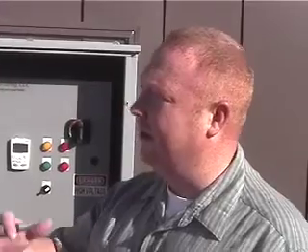Well, that's a very good question. The way this works is we have two different building pressure sensors and a total of 5 relief fans. I believe it's 1, 2, and 5, which is in the middle of the building, and they're the main ones that do the atrium area, that big open space. These 3 fans run together. Our first stage is we modulate the dampers open and closed to relieve the pressure. If we're still above pressure, we would then enable the relief fans to run, and they would all ramp up and down together.